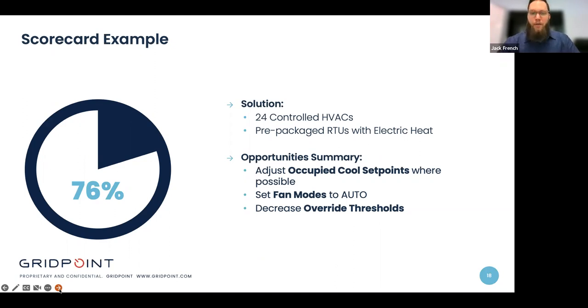Then finally, override thresholds, which we really didn't talk about on the previous slide, but we did talk about on the scorecard definition slide. There were a couple of opportunities for override thresholds being 2 degrees during occupied and 5 degrees during unoccupied. That's pretty standard out of the box. But if you can go 2 degrees occupied, 2 degrees unoccupied, then that'll also help bolster your score, and it'll also help with some marginal energy efficiency gains.